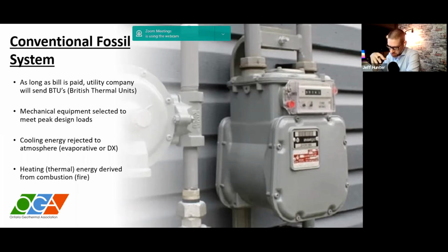Conventionally, when we're looking at mechanical equipment in a building, we're typically sizing to peak loads. We want our equipment to operate in the worst case scenario. Peak load in wintertime, around that design day, occurs maybe 2.5% of the year, and we want occupants comfortable that day. Same thing in the cooling season - we design for the peak there as well, to ensure occupants are comfortable in peak cooling season.